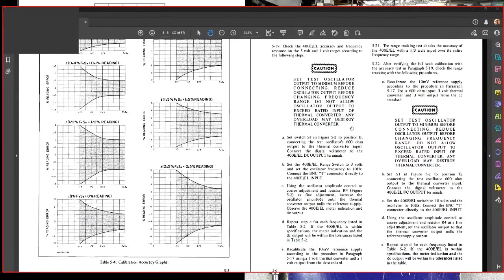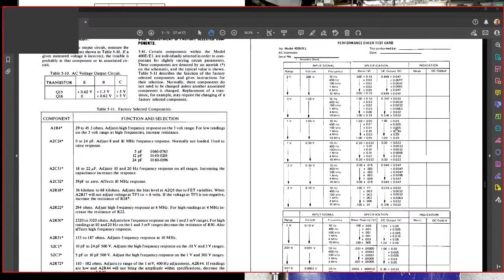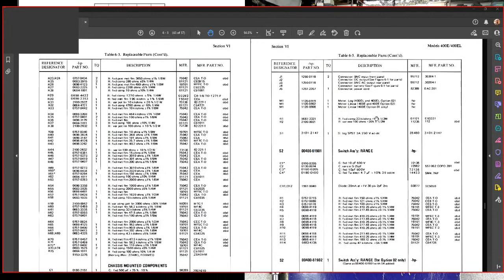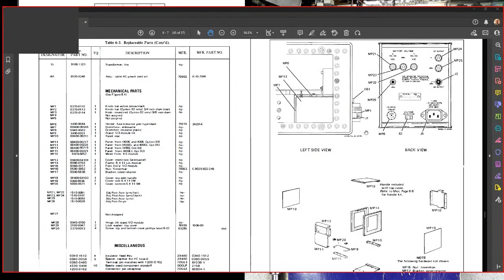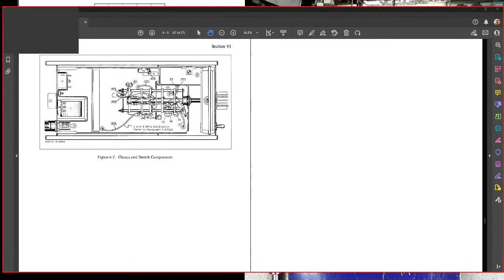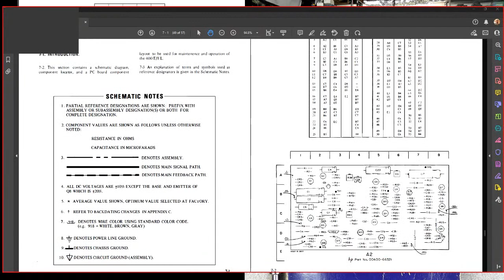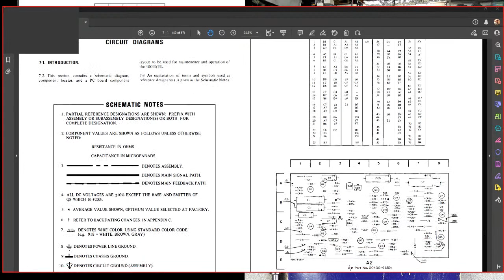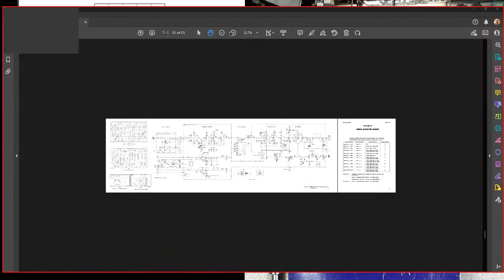the position, right? So let's jump to the schematic. There's all these different internal adjustment locations, where to set them. And this is a test card where you can actually go through all of these measurements and enter in the results. So there's a lot involved to calibrating these. This is why any instrument calibration costs hundreds of dollars, just because it takes a long time and other specialized equipment. The disassembly notes on the rotary switch, the range switch, component locations on the board, and then they'll come to the, why did that flash so suddenly? They'll come to the schematic in just a sec. Here it is. Why is that so small?